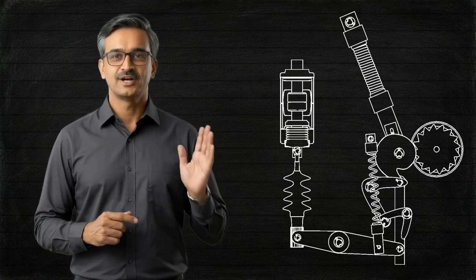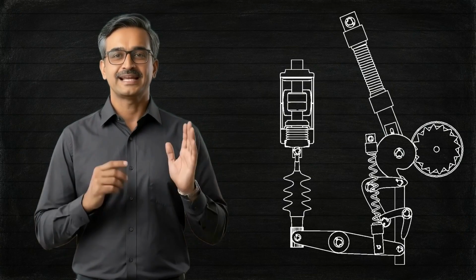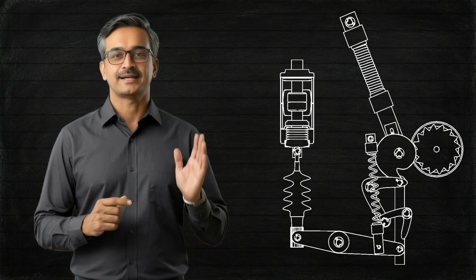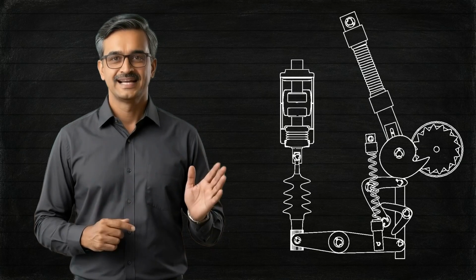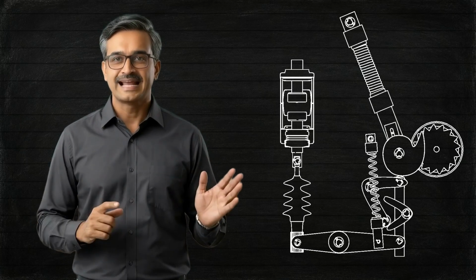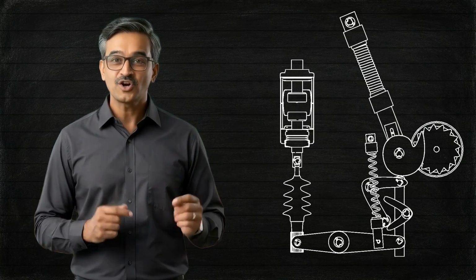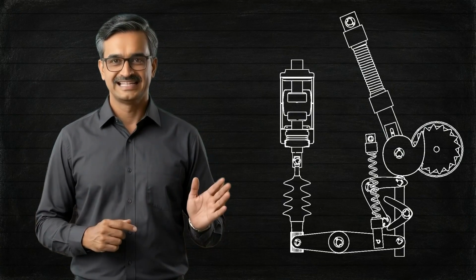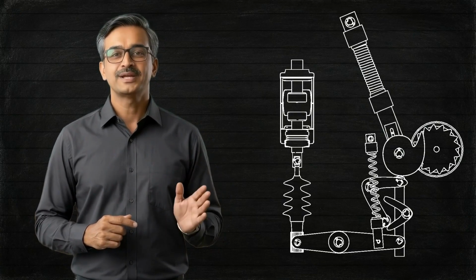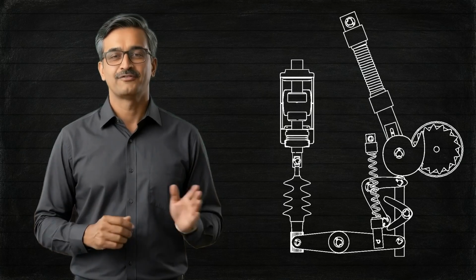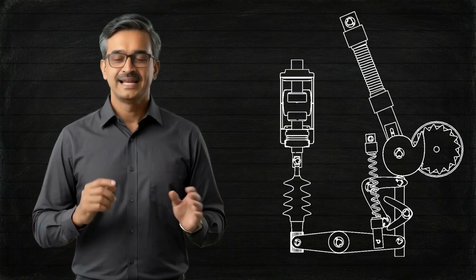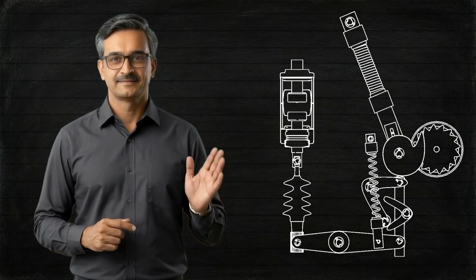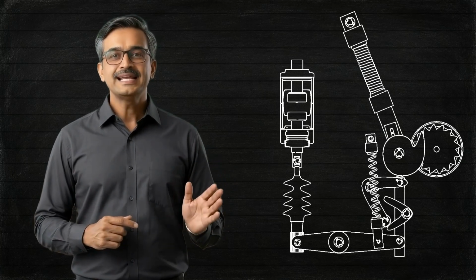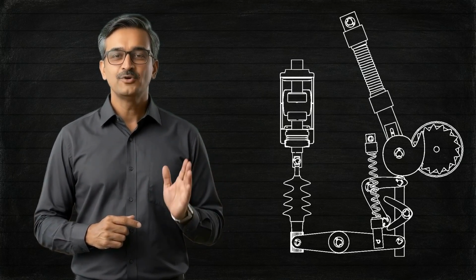Now suppose a fault occurs in the system. A protection relay sends a trip signal to the trip coil. The trip coil releases another latch. Again, remember this carefully. The trip coil does not open the breaker. It only releases the latch. The actual opening force comes from the stored energy of the opening spring. The opening spring expands almost instantly. The moving contacts separate rapidly, interrupting the current and extinguishing the arc.